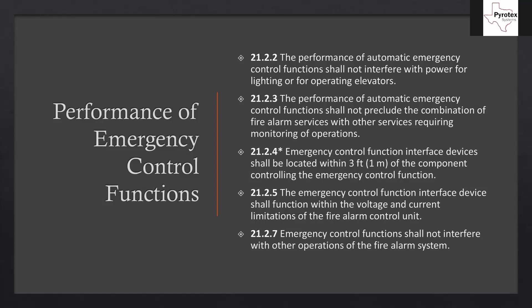Emergency control function interface devices shall be located within three feet of the component controlling the emergency control function. So in an elevator machine room, your relay shutting down the elevator needs to be within three feet of the controller. For air handler units, if there's a VFD in a mechanical room and we put the duct detector up on the ductwork, we need to remote-mount that relay within three feet of that VFD controller. The emergency control function interface device shall also function within the voltage and current limitations of the fire alarm control unit.